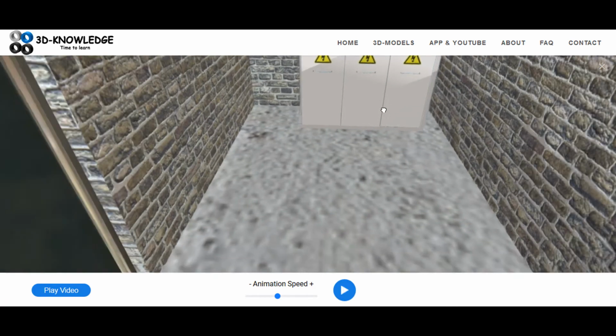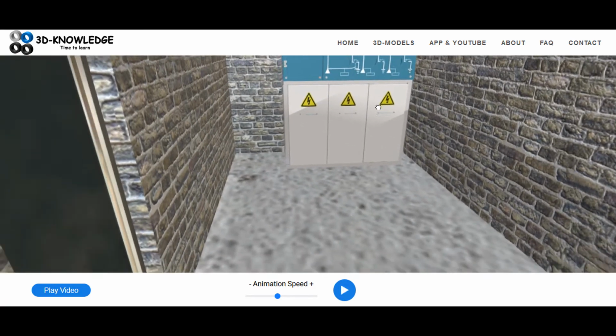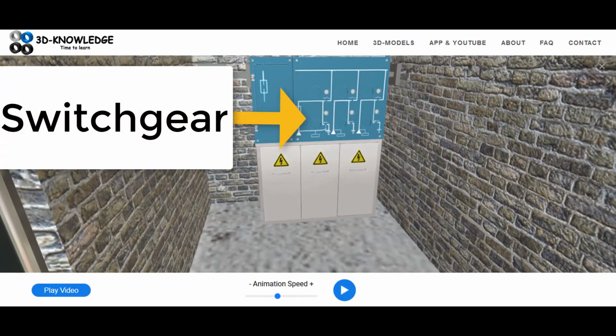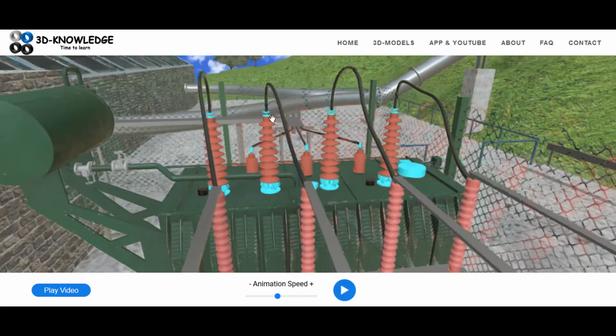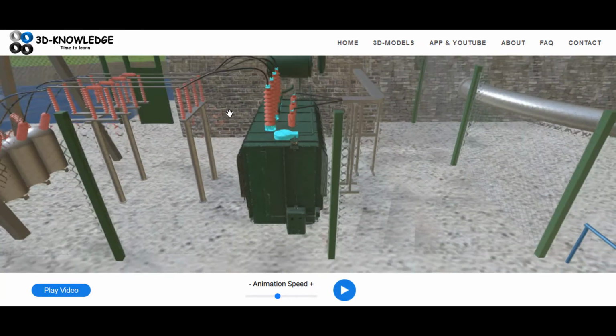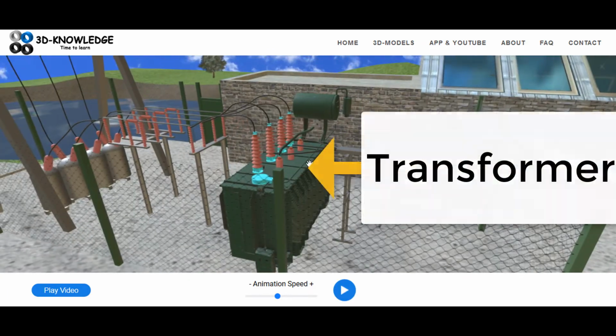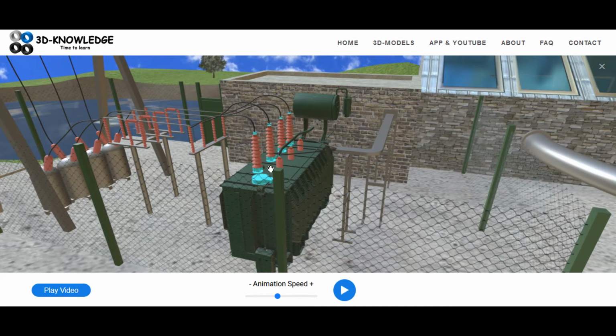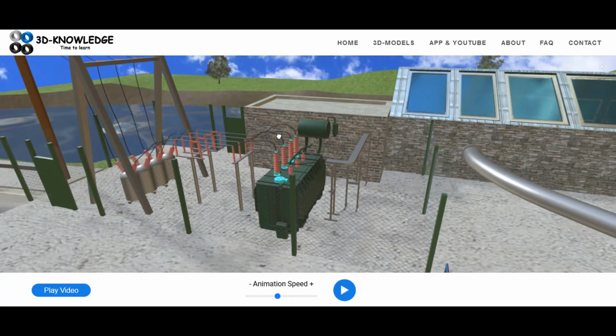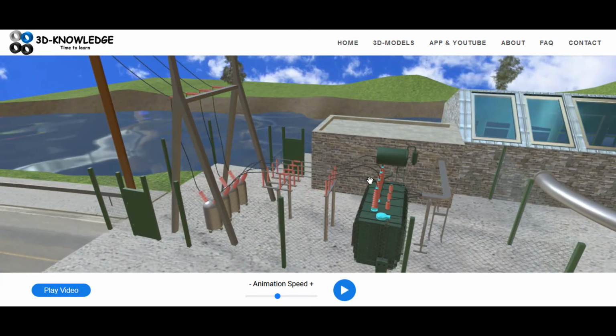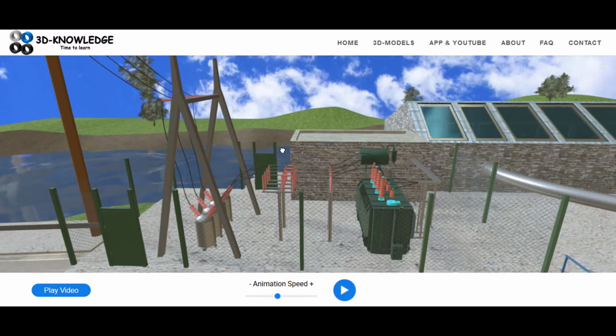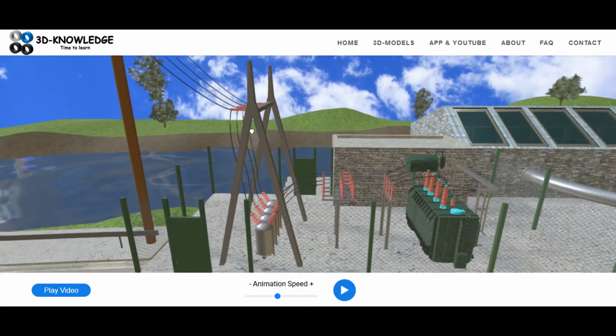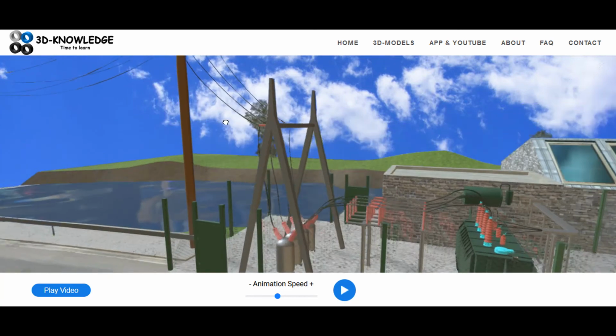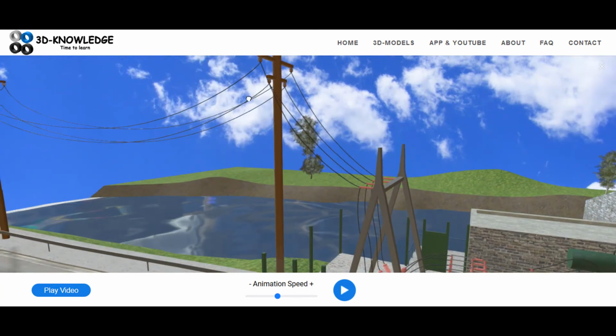What we have here is what we call a switch gear - kind of like a big circuit breaker. The electricity comes out of the generator, goes to the switch gear, comes out of the switch gear, goes to a transformer, and here we increase the voltage from, imagine, 6,000 volts up to 110,000 or 220,000 volts - it depends on your geographical location, but we boost the voltage. It then goes through a current transformer and voltage transformer, maybe a circuit breaker, and into the national grid, which is this here.